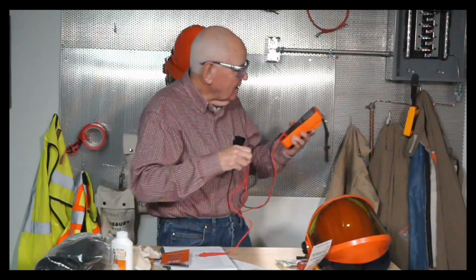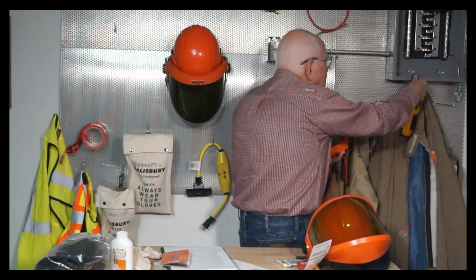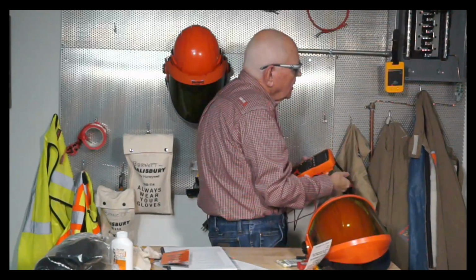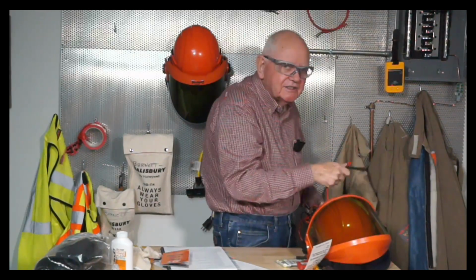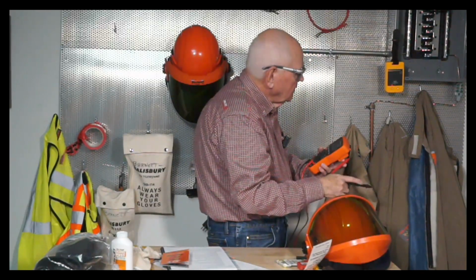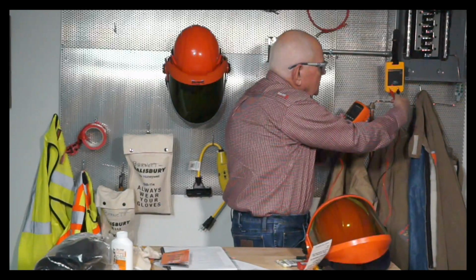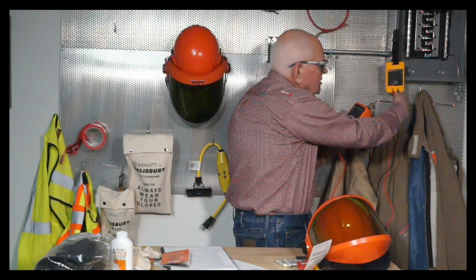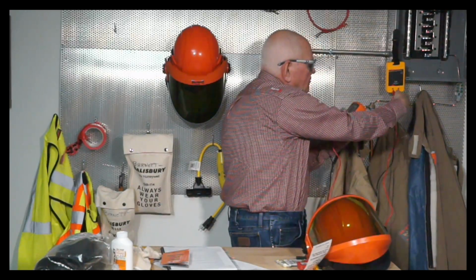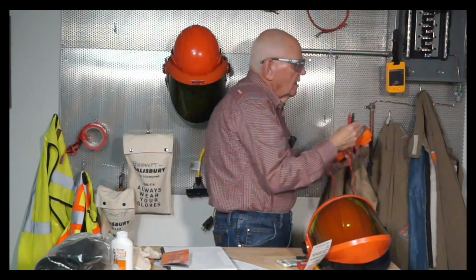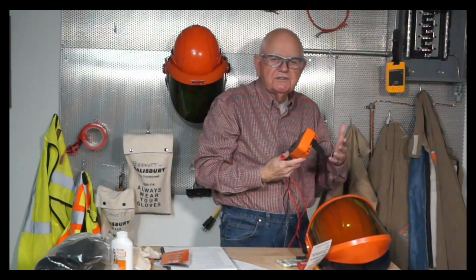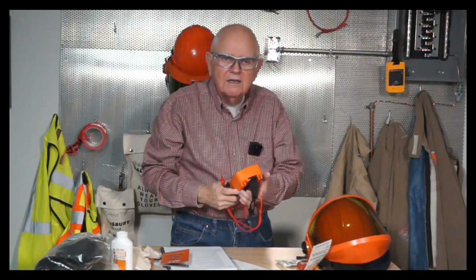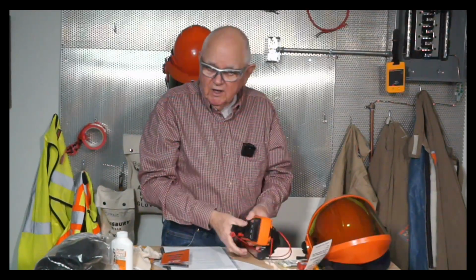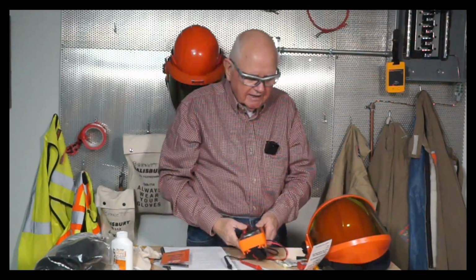And so to do that, we have a proving unit where I can turn the proving unit on. I put it on either AC or DC. And then I just depress the test leads right here where these two little holes are, and I get a reading on my meter of 240 volts, either AC or DC, when I'm testing. So what I've done is I've verified that my meter works on voltage. Very important when we do lockout tagout, isn't it?